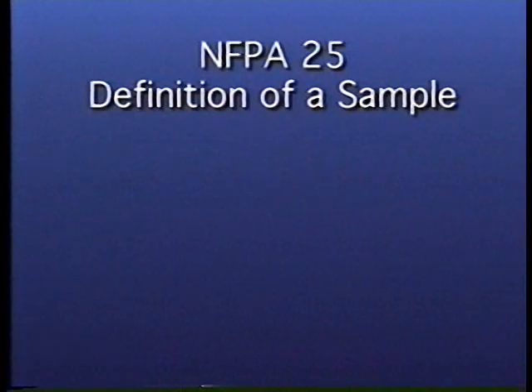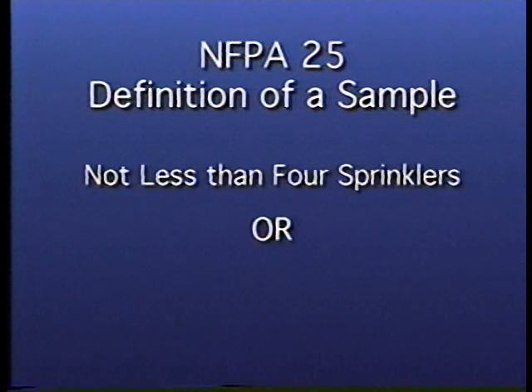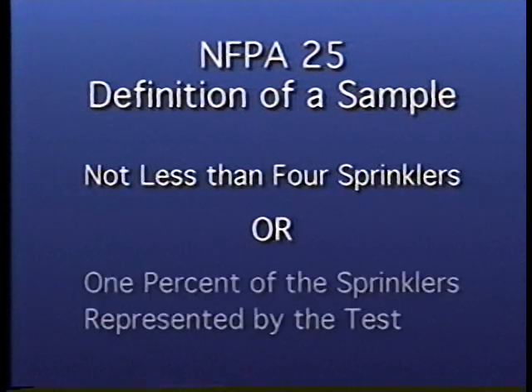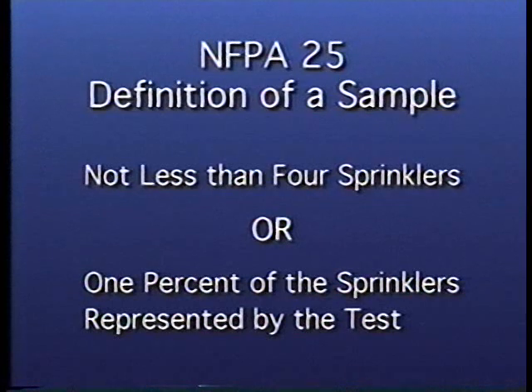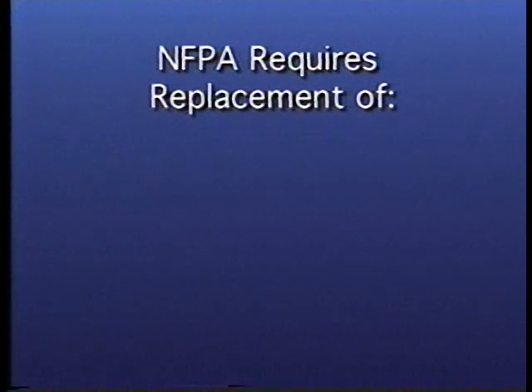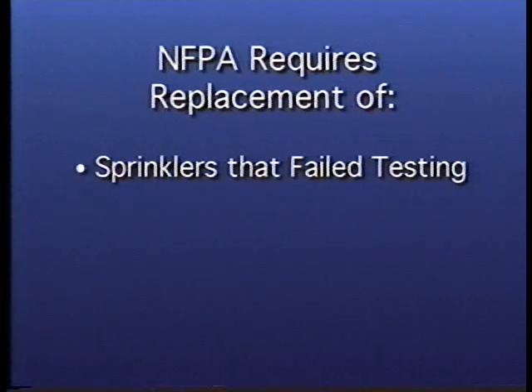The tests involve representative samples of each type of sprinkler by temperature rating and model of sprinkler taken from each hazard area to be tested. The definition of representative sample, according to NFPA 25, is a minimum of not less than 4 sprinklers or 1% of the sprinklers represented by the test. The laboratory then tests the sprinklers and issues a report indicating whether the results were satisfactory or not. If they were unsatisfactory, the remaining sprinklers should be replaced.